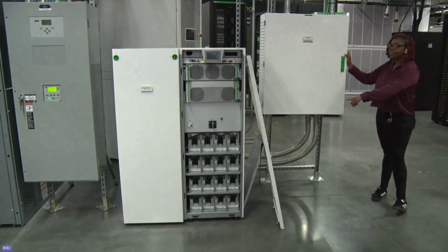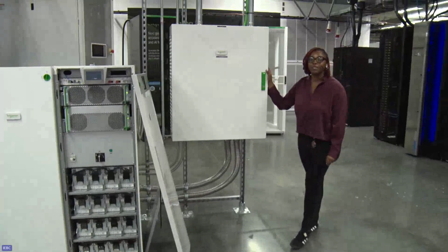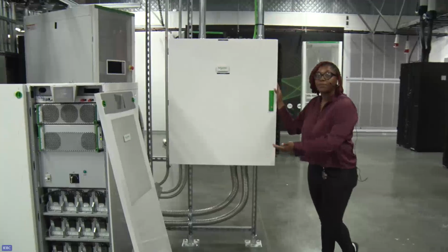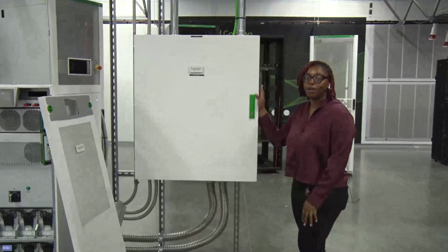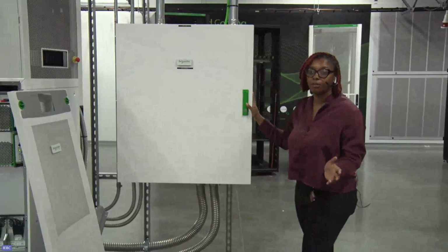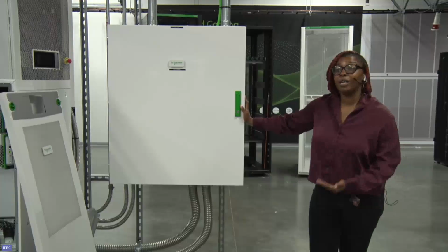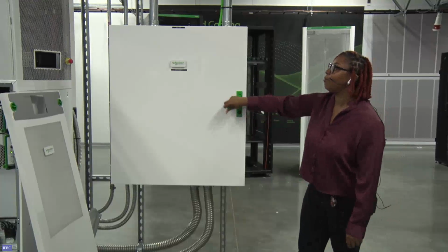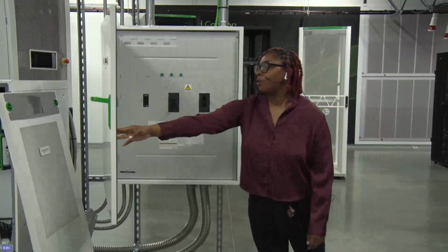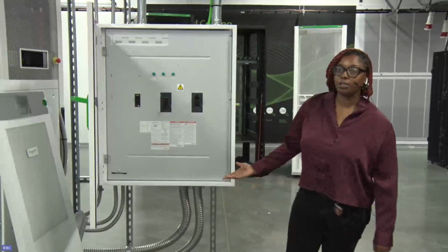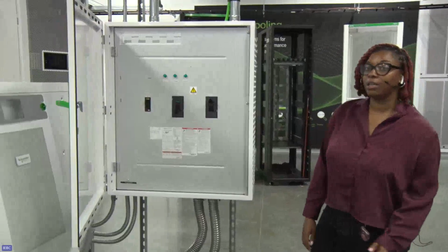Because there are batteries in the bottom of this UPS system, we don't have this space for wiring like we did with our standalone to have the maintenance bypass right next to it as a cabinet. So we have a panel for it. This will go right on the wall, and then you have your 3 breakers as I showed you with the other 2.